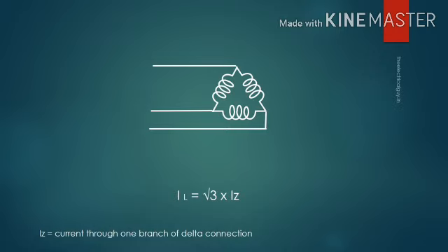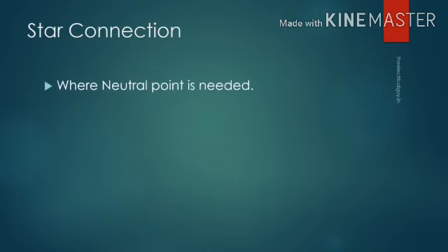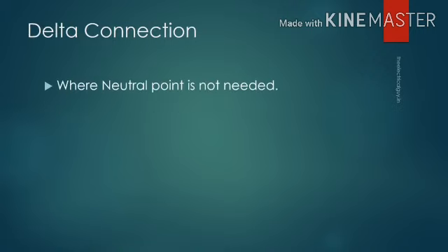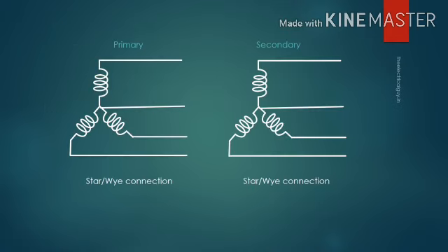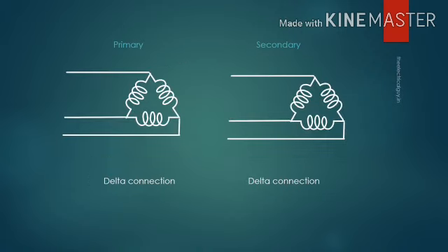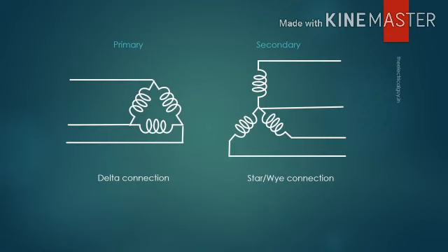Generally, star connection is used where you need a neutral and two separate voltages, like in our distribution system. Delta connection is generally preferred where a neutral conductor is not needed, like in the transmission of high voltage power. Also, delta connection is preferred where third harmonics need to be controlled. Star and delta connections are almost used everywhere when we talk about three-phase systems. You will generally find three-phase transformers connected in different combinations of star and delta connection. For example, a star-star connected transformer is generally used as an auto transformer. A delta-delta connected transformer is generally used for high voltage transmission. And a delta-star connected transformer is generally used as a distribution transformer.